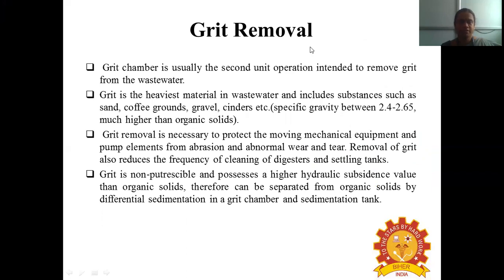The grit chamber is usually the second unit operation, intended to remove grit from wastewater. Grit is the heaviest material in wastewater and includes substances such as sand, coffee grounds, gravel, and cinders. The specific gravity of grit is usually between 2.4 to 2.65, much higher than organic solids. Grit removal is necessary to protect moving mechanical equipment and pump elements from abrasion and abnormal wear. It also reduces the frequency of cleaning of digesters and settling tanks. Grit possesses higher hydraulic subsidence value than organic solids and can be separated by differential sedimentation.